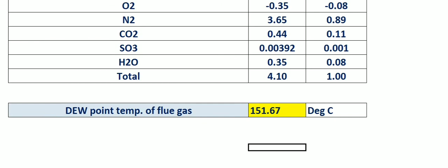Let me recap a bit. First of all, in the flue gas there is a possibility of hot end corrosion and cold end corrosion. Hot end corrosion takes place because of vanadium. One more thing I want to share: whenever the fuel oil has more than 100 ppm of vanadium, and above 200 ppm, there is a differentiation. So we call them low vanadium crude and high vanadium crude. Hot end corrosion takes place above 530 degrees centigrade, which should be avoided, because vanadium formation will be there. Slag deposition will be there in the tubes, the furnace and the duct.